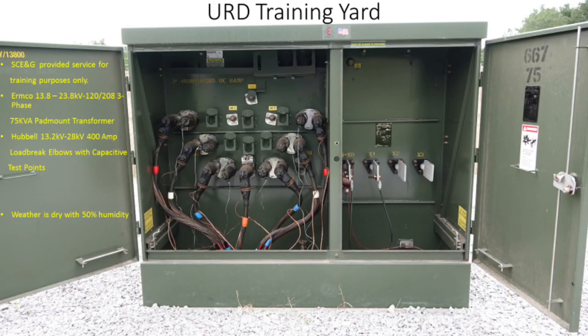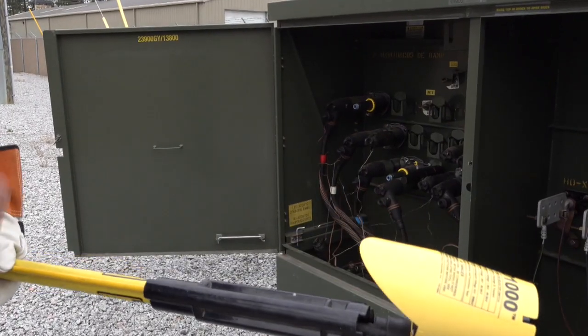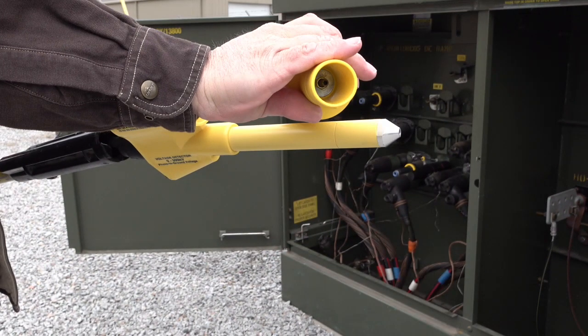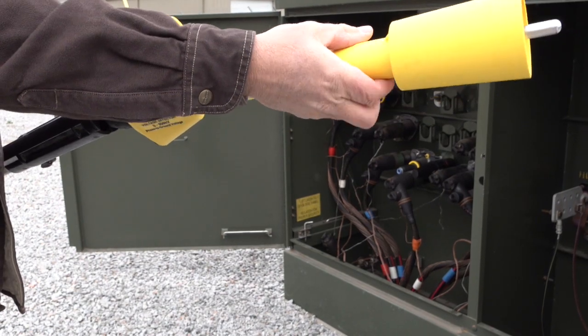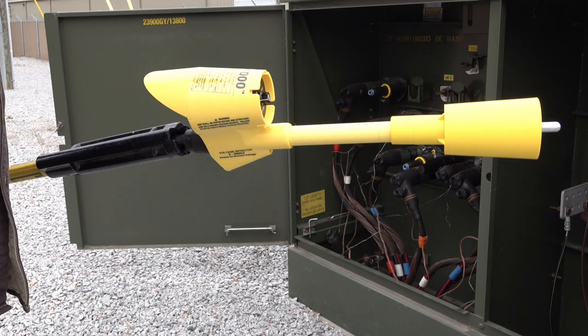All of our underground demonstrations with the VD1000 will be done in this URD 3-phase pad mount. I've added some bullets on the left for additional information and reference. Now that we've performed the self-test and the known voltage test on the VD1000, we can begin our first demonstration. Our first demonstration will require us to take a reading within the pad mount transformer. This will require us to thread our bushing adapter into the tip of the meter probe. Notice the 1/4-20 threads from the bushing adapter that thread into the female 1/4-20 threads on the probe. Now we are ready to take our first reading.